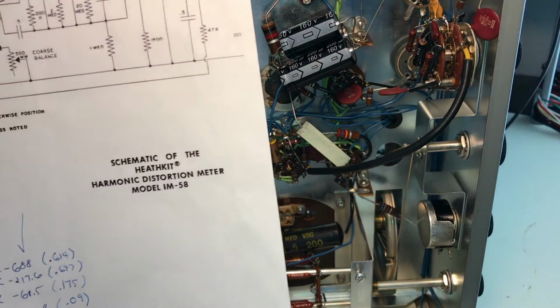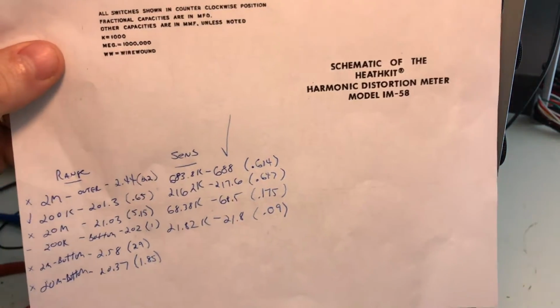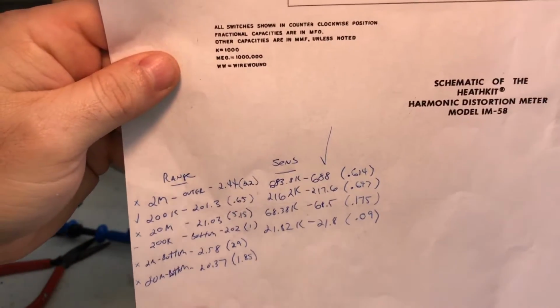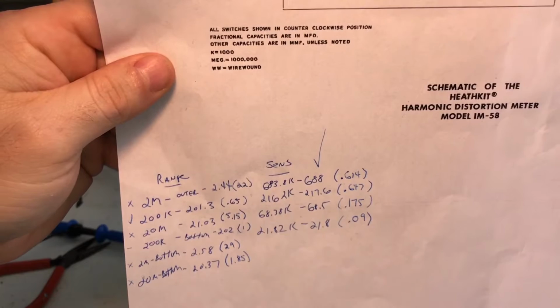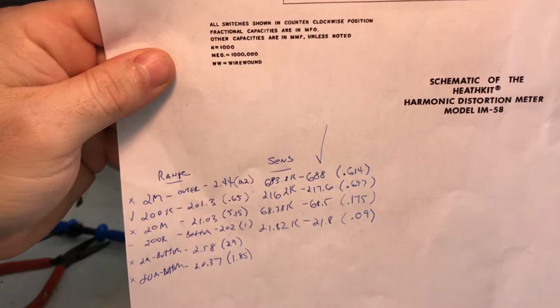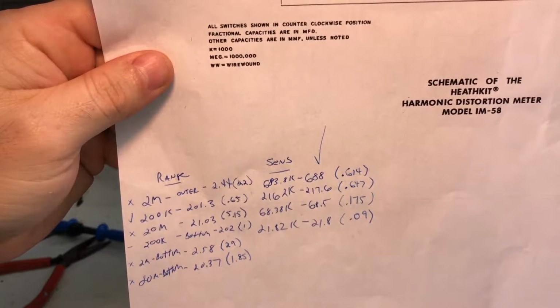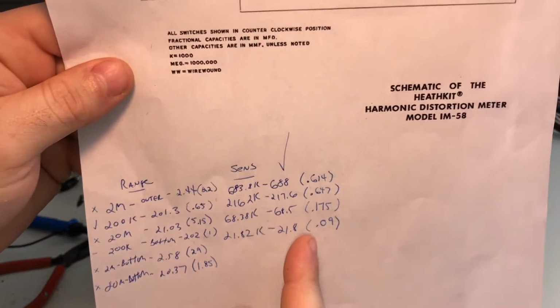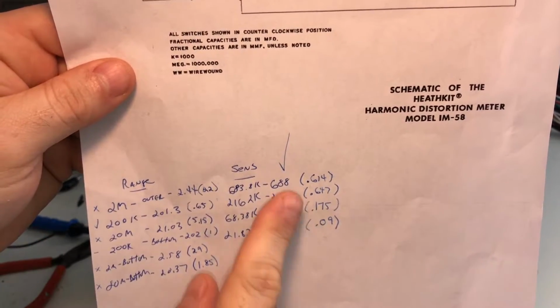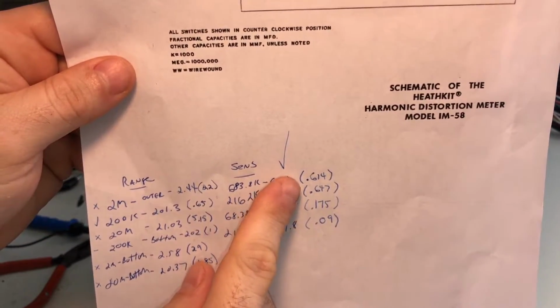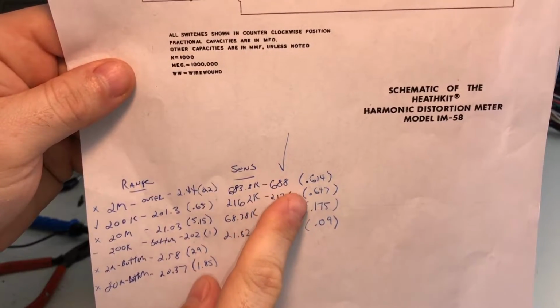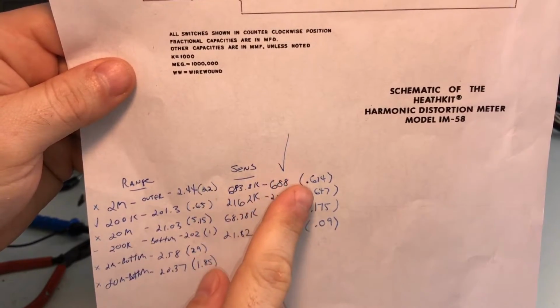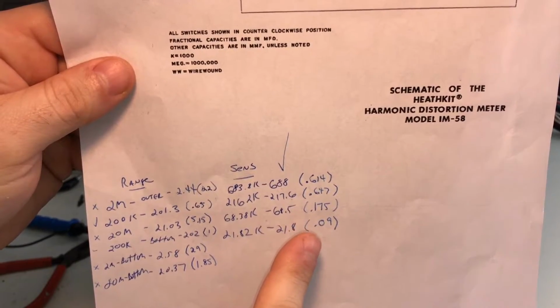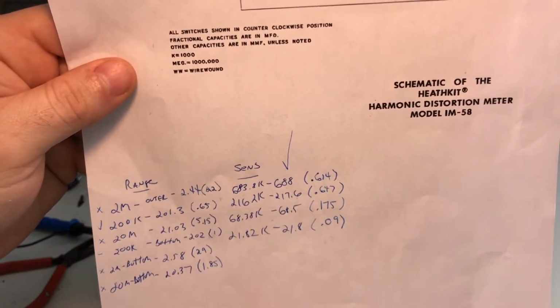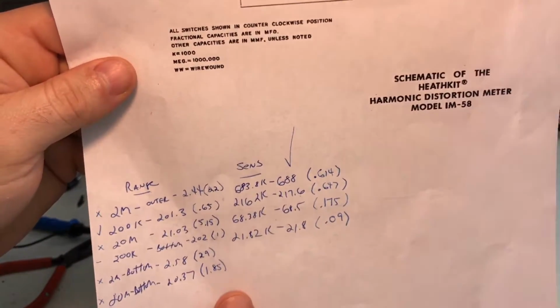I've gone and taken some resistance measurements of some of the precision resistors, or all of them for that matter, and the range switch and the sensitivity switch, and then I checked to see how far out of tolerance they were. I'll tell you quickly, the sensitivity switch, they're all good. The worst is out by 0.64%, well within the 1% tolerance by magnitude, requiring no further action.